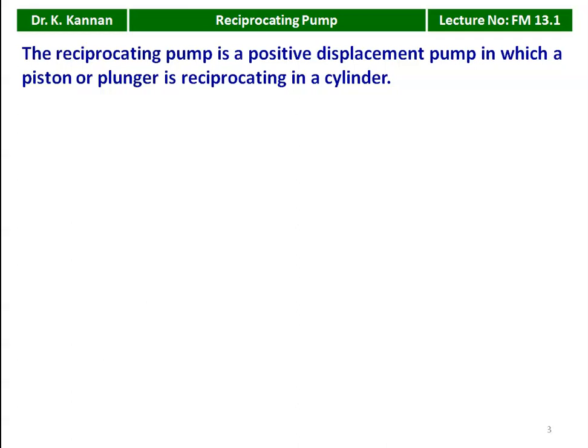A reciprocating pump is a positive displacement pump in which the piston or the plunger is reciprocating inside a cylinder. The positive displacement machine and the rotary machine are the two major classifications. For a rotary machine like the centrifugal pump discussed in the previous chapter, we can close the delivery valve and run it. But for a positive displacement machine, the delivery valve should be in open condition before we start the reciprocating pump — that is the operating condition.